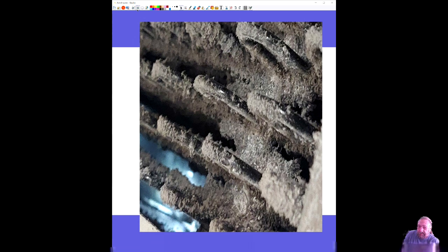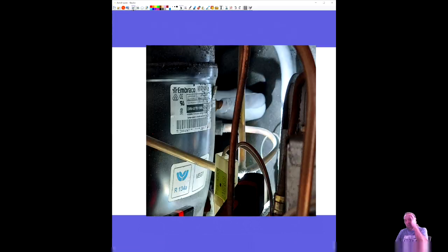And if the fan fails, it should not continue to build up ice and continue to build up ice and never defrost the ice off the unit. So we could have a bad fan problem, but I want to go back to this first picture because I'm still holding back something that I haven't shown you guys yet. What else do you see there? I'm reaching here. This is not a cut and dry answer, but what else do you see here?